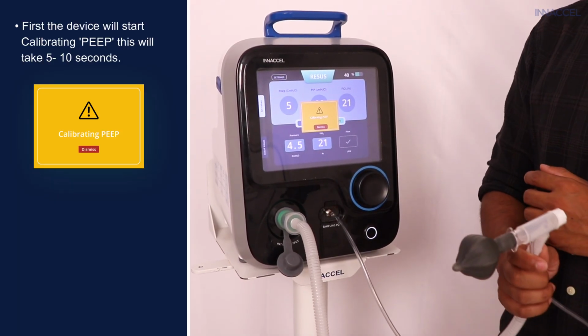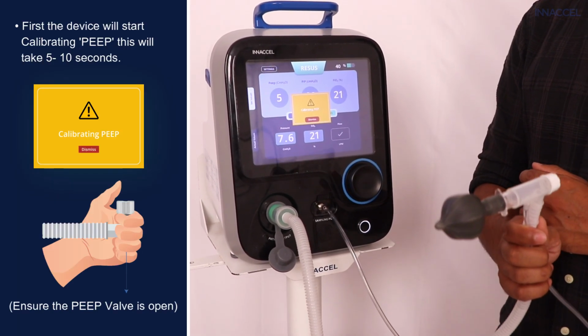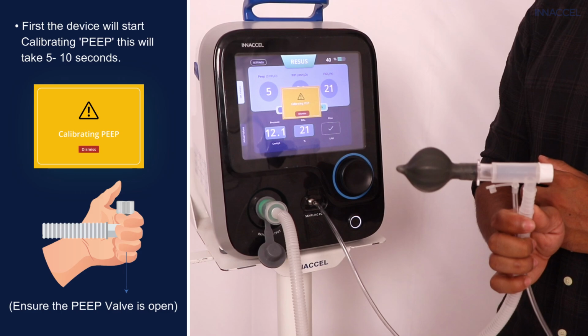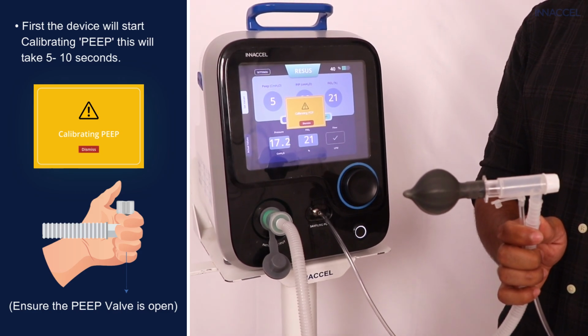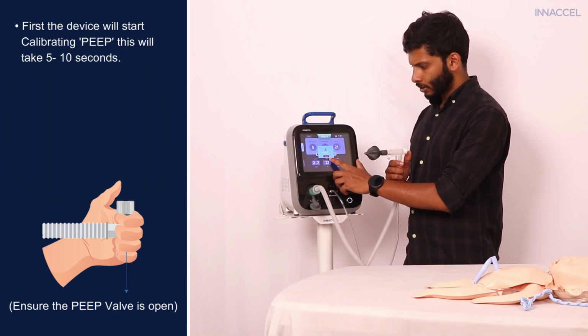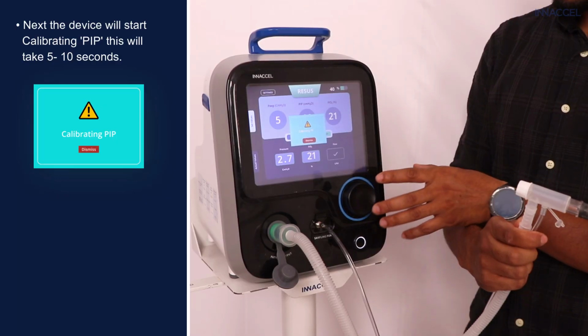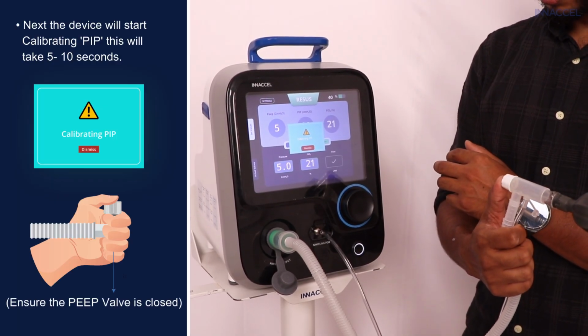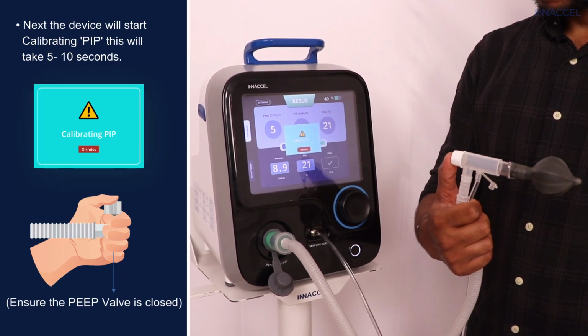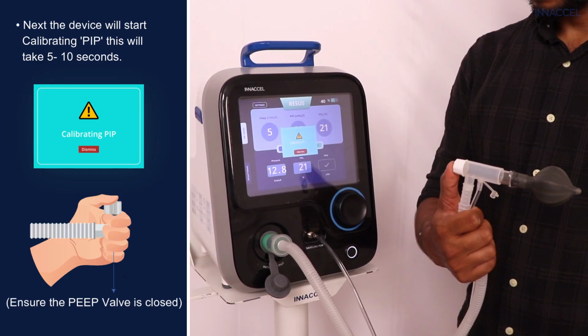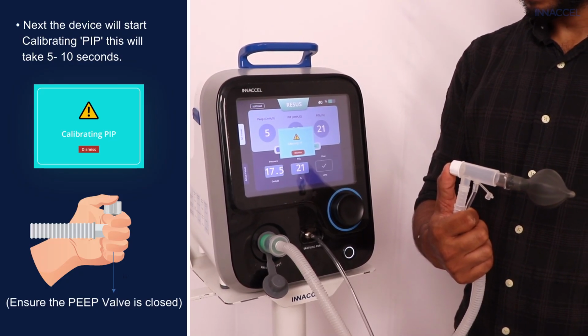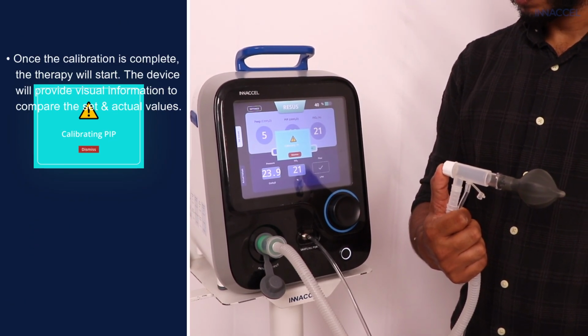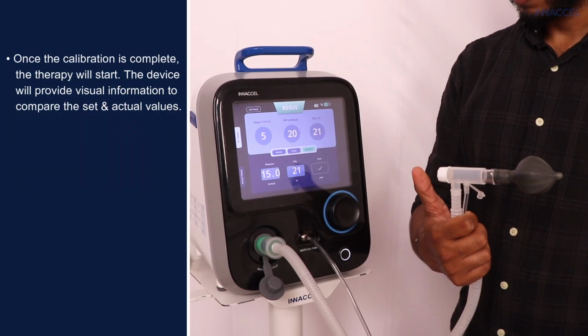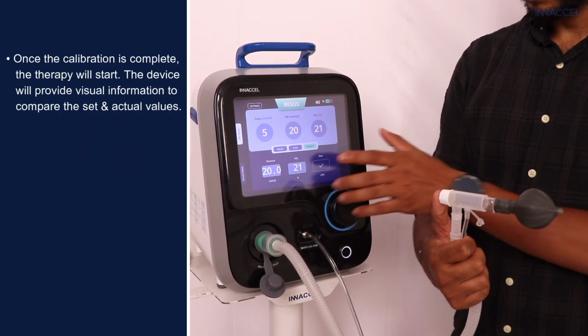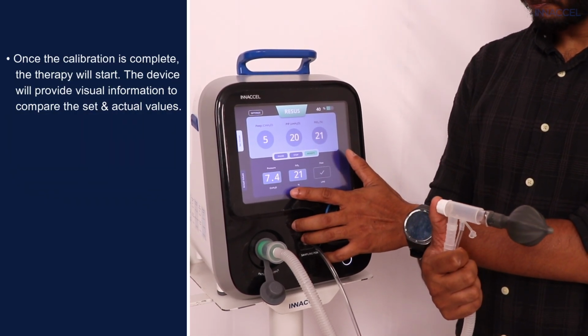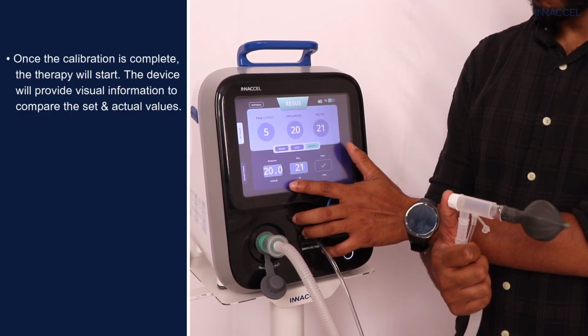This will take 5 to 10 seconds. Ensure the PEEP valve is open. After the PEEP calibration is complete, the device will start PIP calibration. For this calibration, close the PEEP valve using your thumb. The calibration will take 5 to 10 seconds. Once the calibration is complete, the therapy will start. The device will provide visual information to compare the set and actual values.